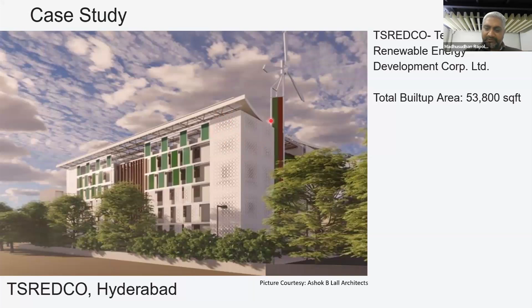And the way this has been achieved is to hybridize structure cooling with radiant cooling, where for most parts of the year, the radiant cooling system works as structure cooling with a cooling tower basically providing the cooling. Of course, dehumidification is being done using a chiller, but the main sensible cooling is being done just using the cooling tower. And in monsoon, of course, we require to use chillers for both systems. But since you have not allowed the heat to accumulate in the summer, the heat being radiated even in June, July would be much lower.